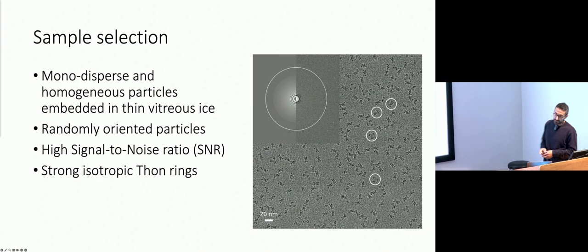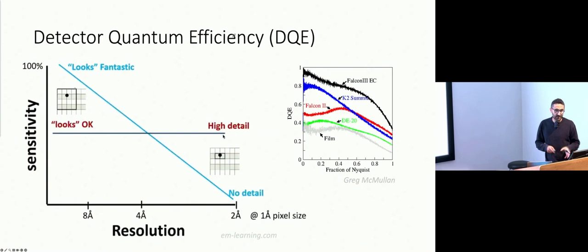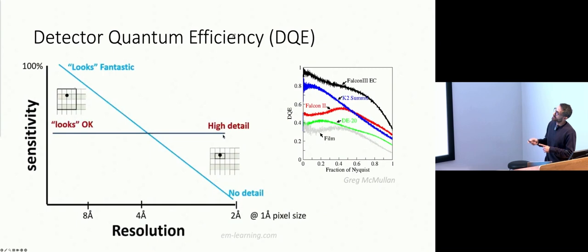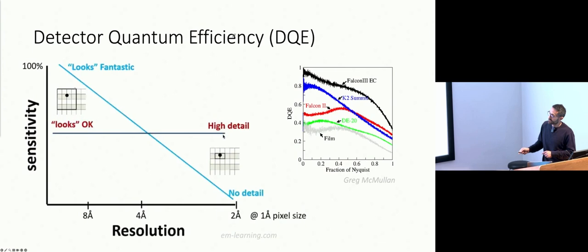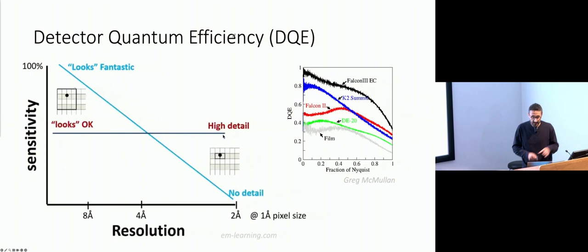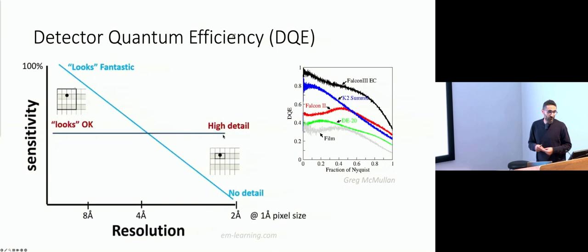Once you have selected the right sample, the next question is the detector. Greg yesterday already spoke about detectors and how they work. The key thing to take into account is the DQE — Detector Quantum Efficiency. In layman's terms, the DQE tells us how good our detector is as a function of spatial frequencies, with the highest spatial frequencies being our Nyquist, which is twice the pixel size.